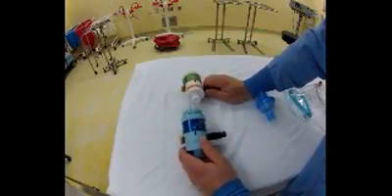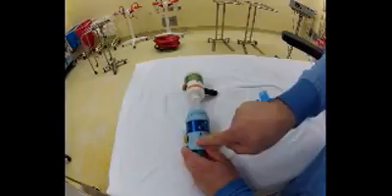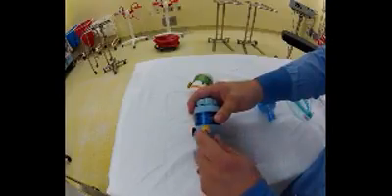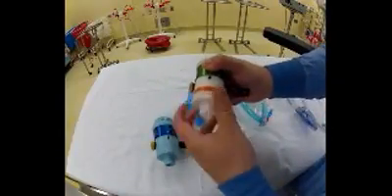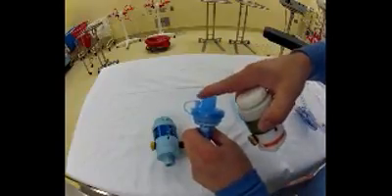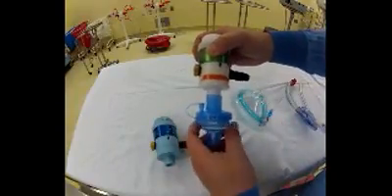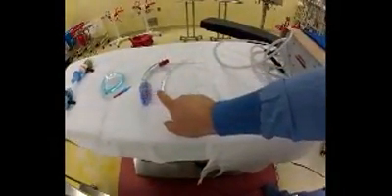These devices flow 30 liters a minute on the maximal inhalation phase during the automatic cycling mode when the gold buttons are depressed and locked down. The units are used typically either with an internal filter that fits underneath the nozzle right here, or they are used with a HEPA filter. This is a HEPA filter that has a tie-in for a side stream capnography hose.